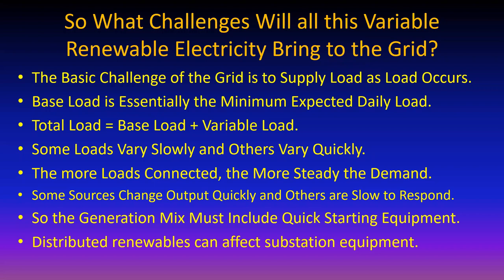Another concern over distributed renewables is when the sun goes under a cloud, all of a sudden all these neighborhood sources stop adding electricity to the grid, and the utility has to add more. There are utility engineers on the webinar who know that the contacts on transformers and substations are mechanical for the most part, and the more they switch back and forth, even in oil, there's some arcing, and they wear out faster, costing money to replace.